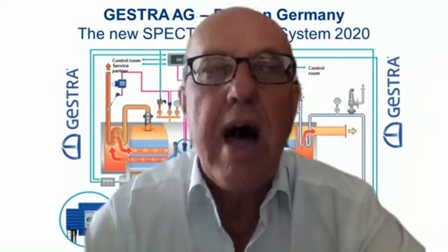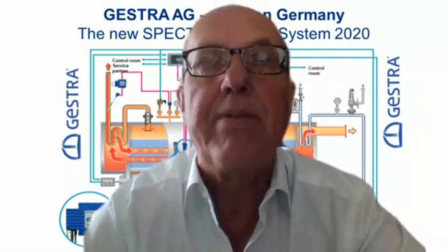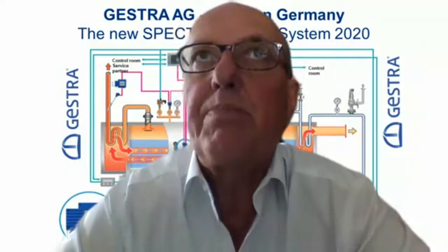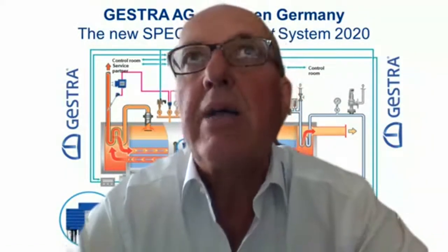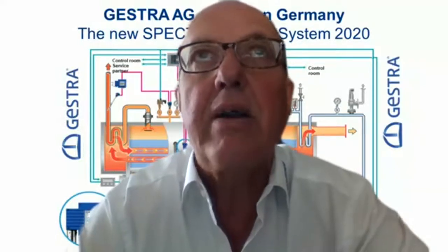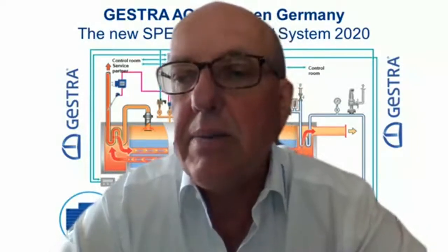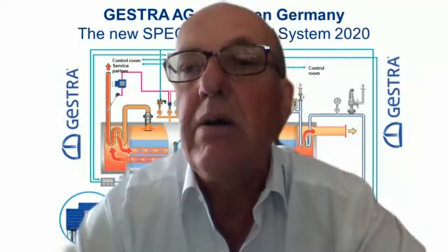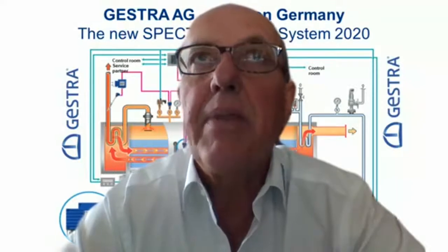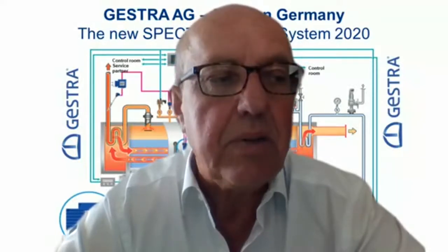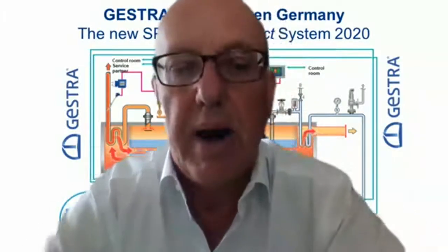So-called vaposcopes are able to show exactly what happens inside the steam trap. They must be installed in front of the steam trap, because behind the steam trap we have flash steam, and the flash steam is not indicating the right working principle of a steam trap, but that is what we can do there. What I said in my seminar, I recommend once a year on a thermostatic steam trap to clean the strainer. And then I want to talk about the supervision of steam traps with an ultrasonic device.